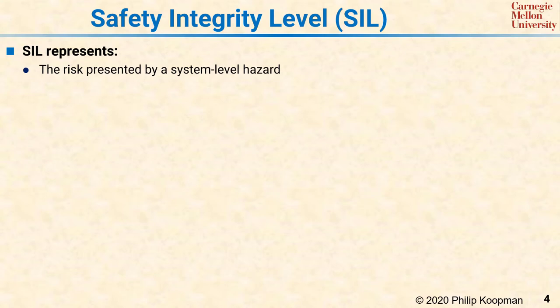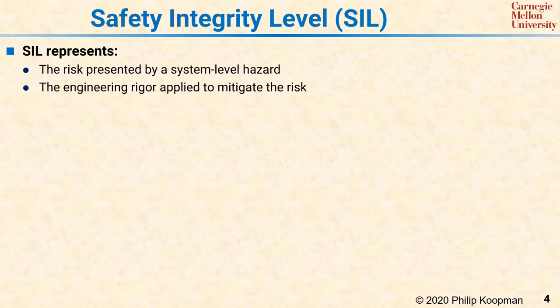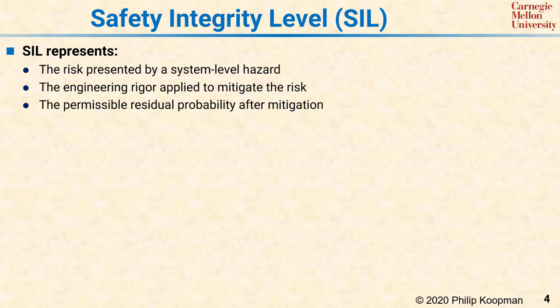Second, a SIL is used to define the amount of engineering rigor and system cost that is applied to mitigate that risk. Third, a SIL is associated with an acceptable target for the residual probability of system failure after mitigation has been completed.